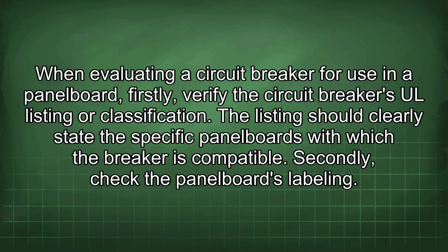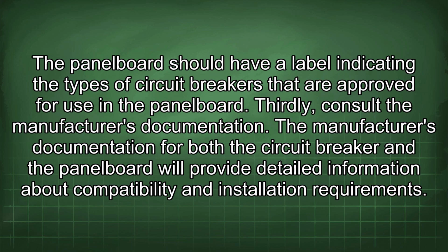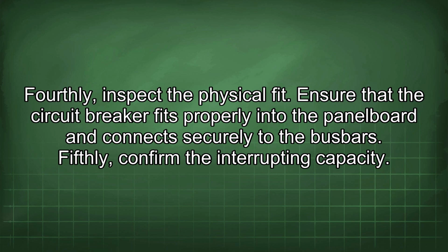Secondly, check the panelboard's labeling. The panelboard should have a label indicating the types of circuit breakers that are approved for use in the panelboard. Thirdly, consult the manufacturer's documentation. The manufacturer's documentation for both the circuit breaker and the panelboard will provide detailed information about compatibility and installation requirements. Fourthly, inspect the physical fit. Ensure that the circuit breaker fits properly into the panelboard and connects securely to the bus bars.